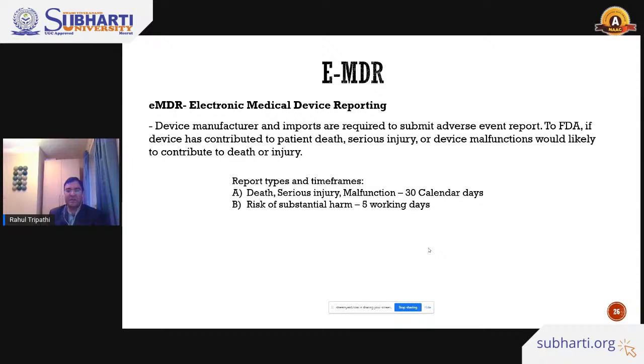And also FDA puts some time frames. Once a death has happened with a certain medical device, that needs to be reported to the FDA within 30 calendar days. If there is a serious injury or the device is malfunctioning, if a pacemaker is not working, or a cardiac stent is causing serious injury or death, the manufacturer needs to report within 30 calendar days. That's the key thing, and it gives FDA more insight into the medical devices. And if the medical device is risky and giving substantial harm, that needs to be reported within 5 working days. So the supplier or manufacturer needs to report within those set time frames.